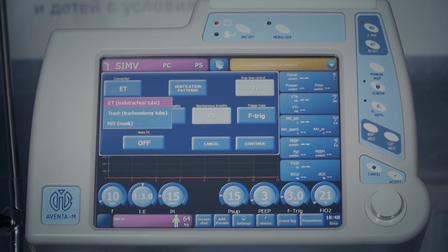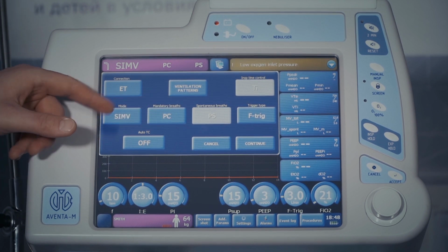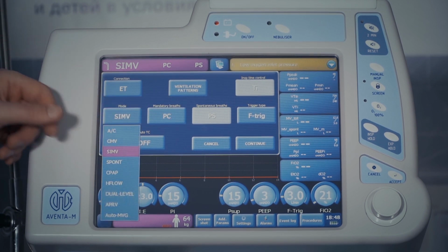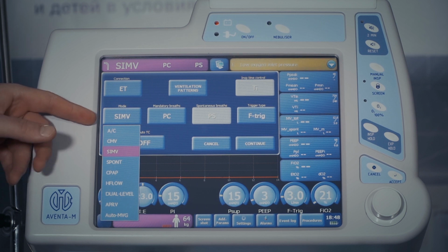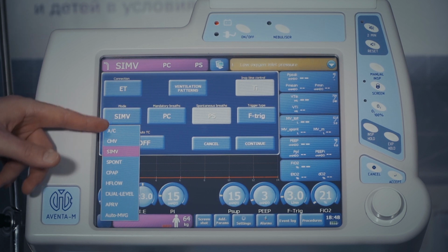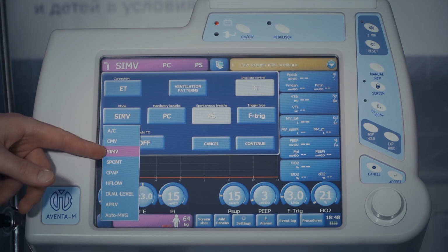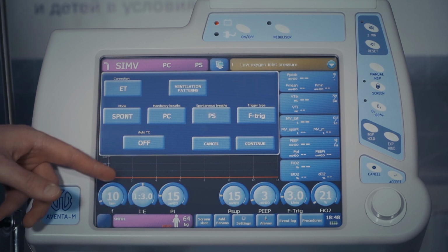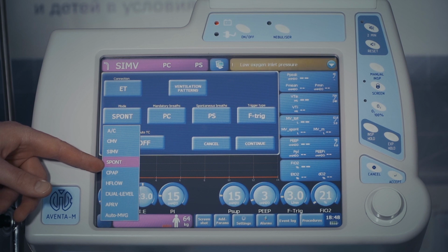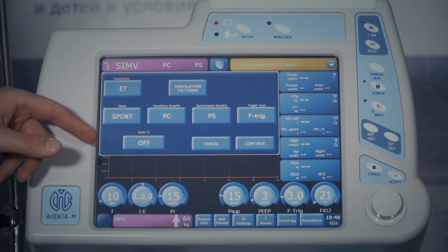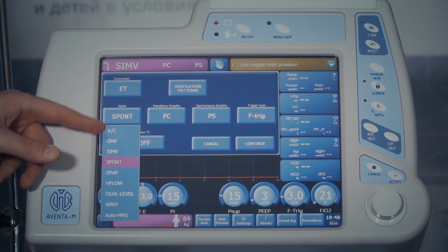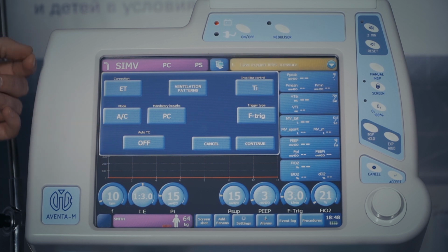The type of patient's connection to the ventilator shall be set in the following window. This can be endotracheal tube, tracheostomy tube, or mask for non-invasive ventilation. Besides, ventilation mode, type of mandatory breath, type of spontaneous breathing, type of trigger, tube resistance compensation shall be set in this window. Press the corresponding button and select the desired value in the opened context menu.